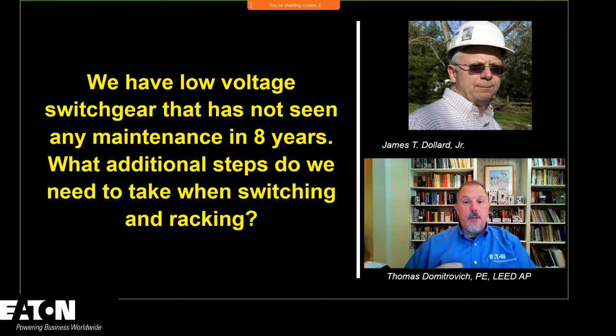So I always say, obviously, NFPA 70B is focused on maintenance, but we always try to make sure that people understand the manufacturer is going to give you guidance on how to properly maintain and the frequencies of those. We do fall back on NFPA 70B as well. But so Jim, you have a piece of equipment, and 70E references hazard awareness and whatnot. You've got to do that hazard analysis, and a piece of equipment that's not maintained or hasn't been maintained, how do you handle that?